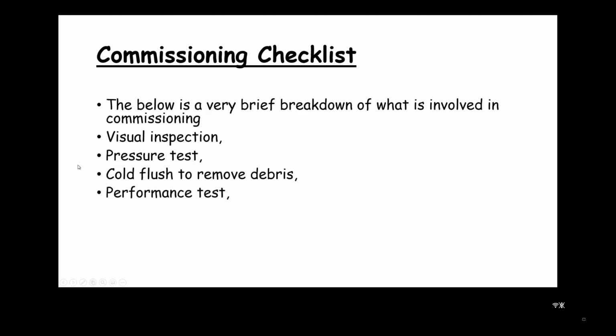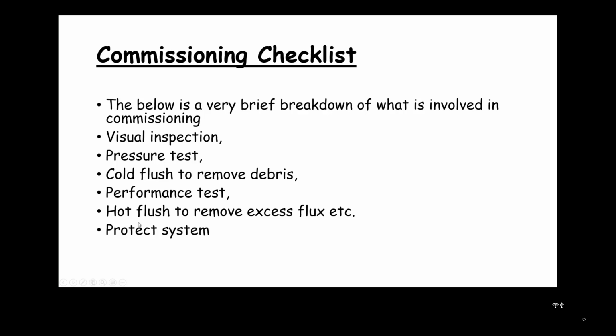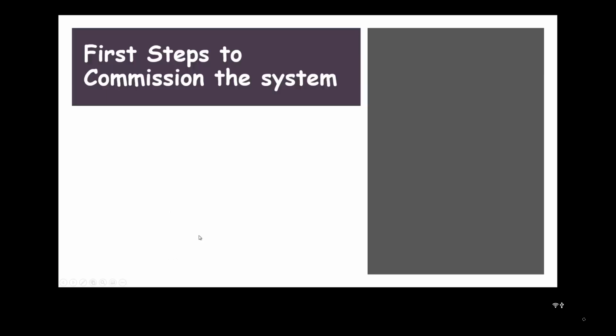And once you've done that, you then refill it and carry out a performance test. That's where you check that everything's working the way that it should. After the performance test, you might want to do a hot flush, and that would help remove excess flux. And then finally, you'd do your final fill and protect the system as part of your final fill, and then take the appropriate steps for handover, explaining to the customer how the system works, etc. And we're going to look at each of those steps now.